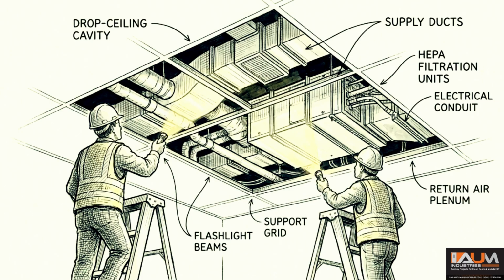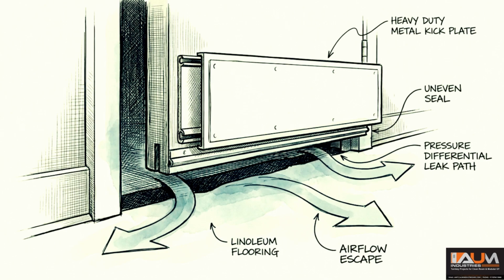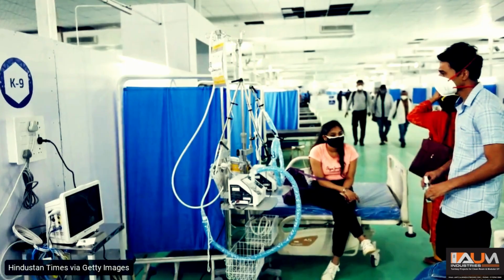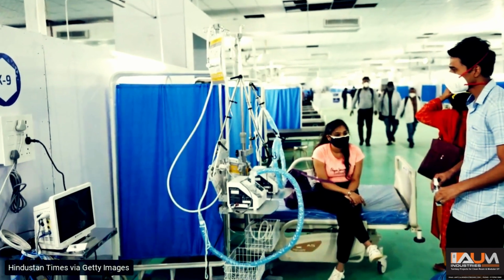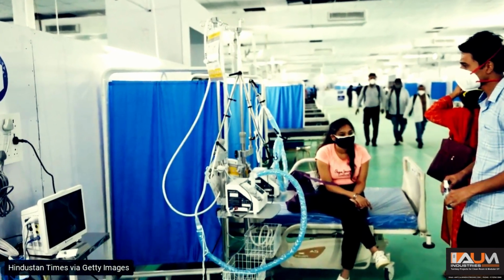The engineering teams scramble to check the ductwork and the filtration units, but the source of the pressure drop is often found right at the physical door frame. In critical care environments, a door is a primary infection control system. If it fails, the entire room fails with it.